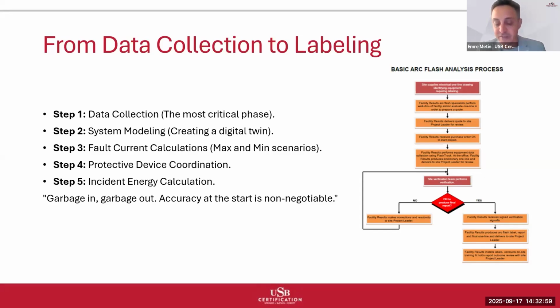I cannot overemphasize how critical accuracy is at this stage. I have seen analyses that were completely invalid because the input data assumed certain protective device settings that didn't match the actual installed settings. Step 2, system modeling. We call it now a digital twin. Using specialized software like ETAP, we create what's essentially a digital twin of your electrical system. Every transformer, every conductor run, every protective device gets modeled with its specific characteristics. This model must accurately represent not just the equipment nameplate data, but the actual as-built and as-configured system.